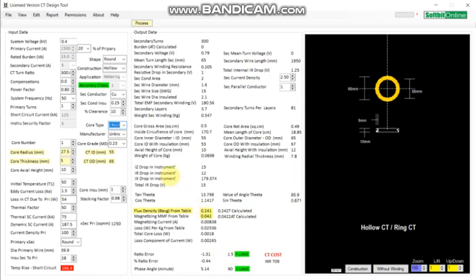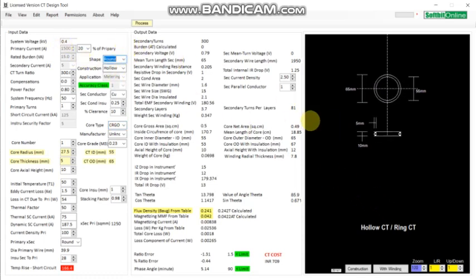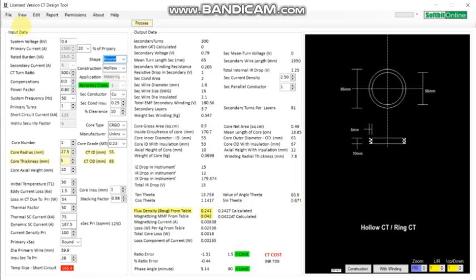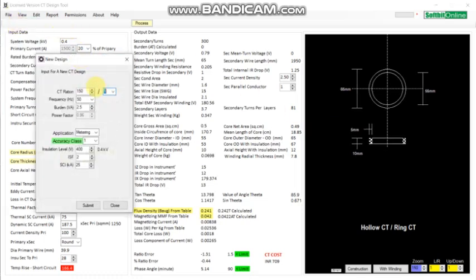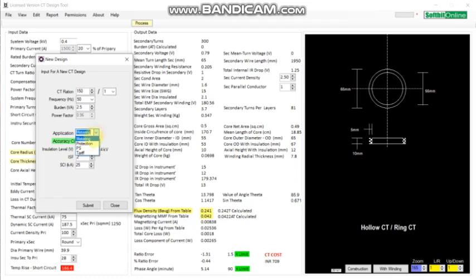So let us design a new CT. We enter a 150 by 1 ratio, 50 Hz, 2.5 VA burden, power factor 0.96. We are going to design a metering CT. Accuracy class available is 1, 3, or 5. If you go for a tariff CT you have accuracy class 0.2 or 0.5S.